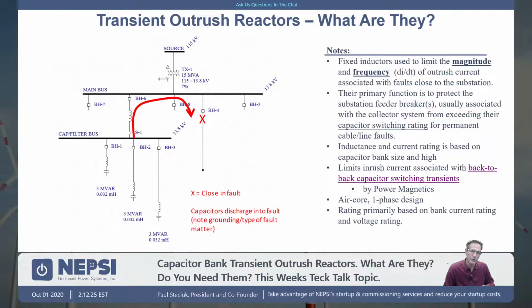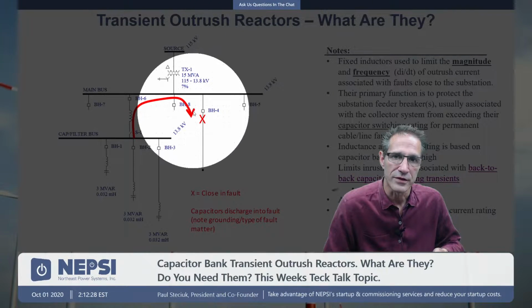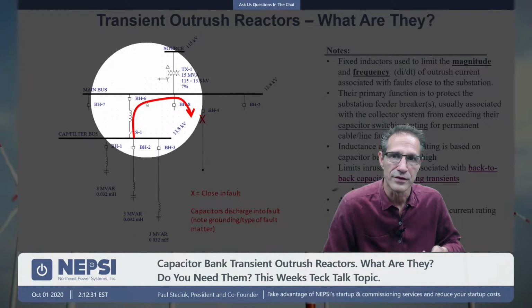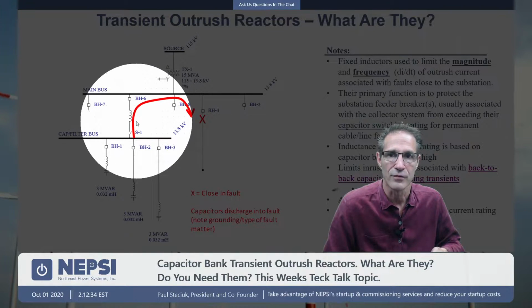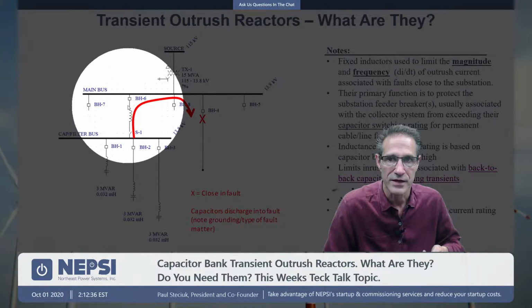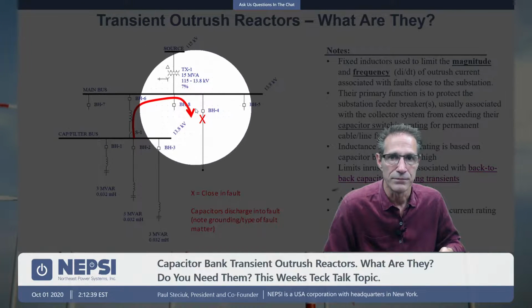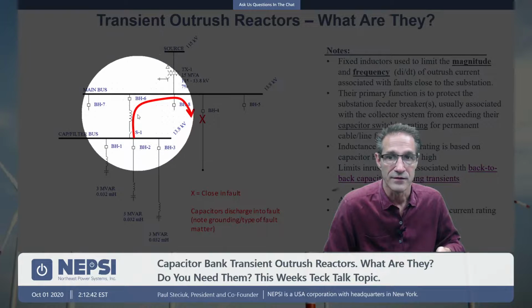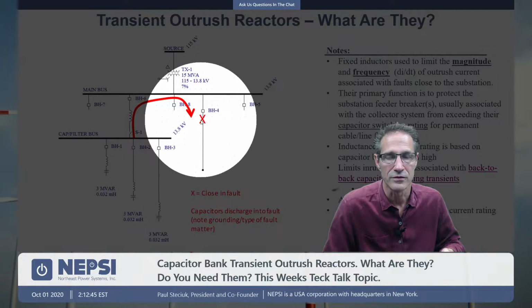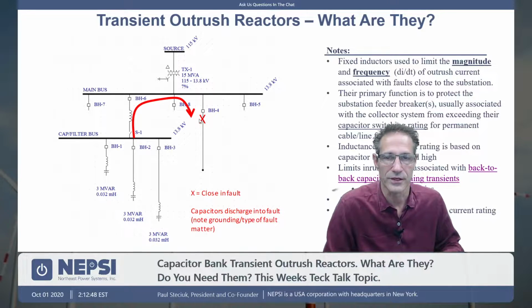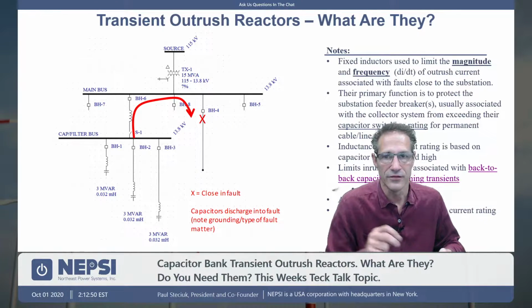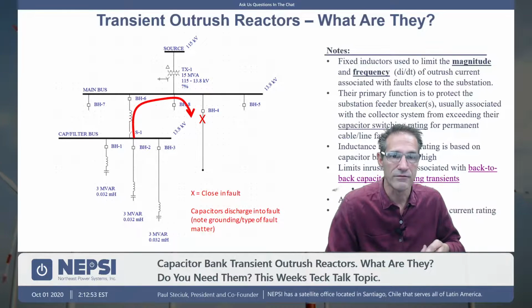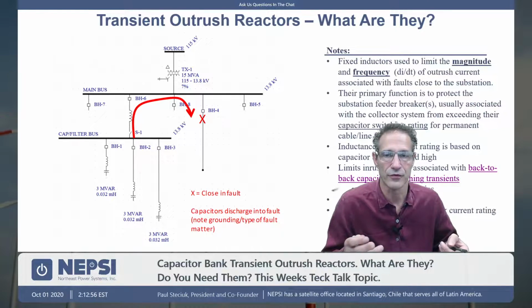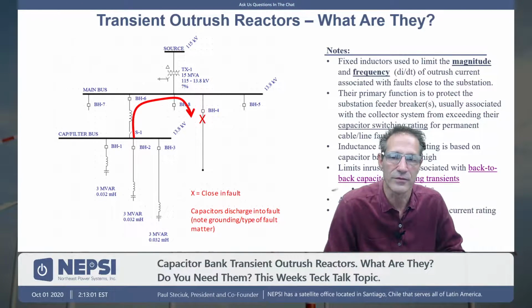So when you do close BH4, the only impedance in the circuit that reduces the magnitude and the frequency of that current flow is the impedance of the cabling, the impedance of the buswork, and the impedance to the fault. That's it. And if it's a close-in fault, and we call it a close-in fault, say right outside of the substation, that would be a close-in fault. And think of this inductance of the cabling as 0.5 microhenries per foot. So whatever you have for distance, 0.5 microhenries per foot. It's a good rule of thumb. Sometimes maybe slightly less, but 0.5 microhenries per foot. It is that impedance that will limit that fault current.